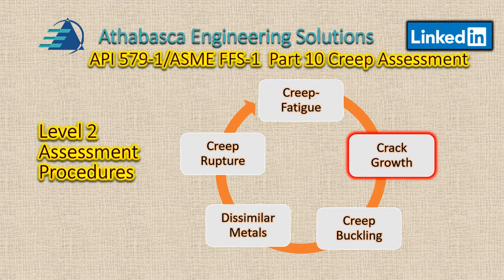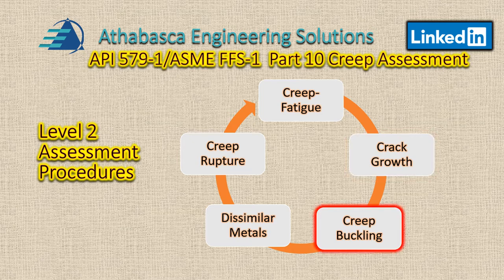CREEP crack growth refers to components that are subject to either a steady-state condition or cyclic operation in the CREEP range, which may contain crack-like flaws. CREEP buckling refers to the time at which a component in the CREEP range may be subject to structural instability, meaning it could collapse due to a compressive stress field.